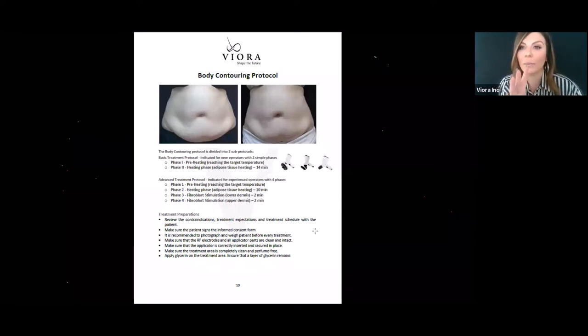Okay, so preheat them in mode 4. Now we go to mode 1, our deepest depth, and we set the timer for 10 minutes. You're going to keep the vacuum high if possible, because remember the positives of the vacuum. We're increasing circulation, we're increasing depth of penetration. For cellulite, we're massaging septae. For contouring, we're increasing the metabolism and working with the lymphatics, all of the excess fluids within the area. So the higher the vacuum you can keep it, the better you will be when you're in mode 1. Your RF level will just be whatever it needs to be to maintain that 39 to 42 degrees. So if you're at RF4, you can keep it there. If you start going way over temperature, you're hitting 43, 44, 45 degrees, then just drop your RF level down.